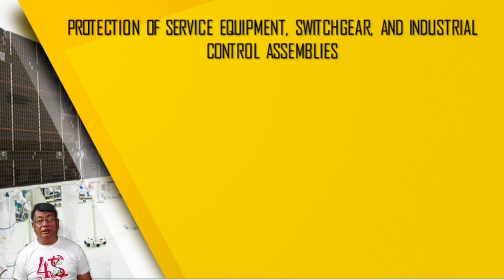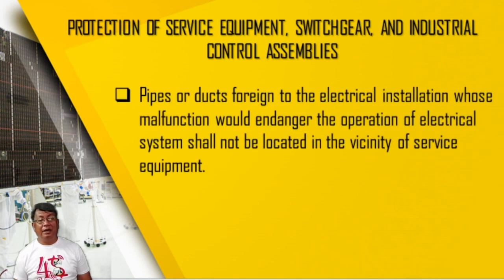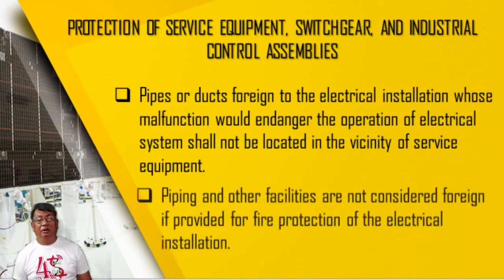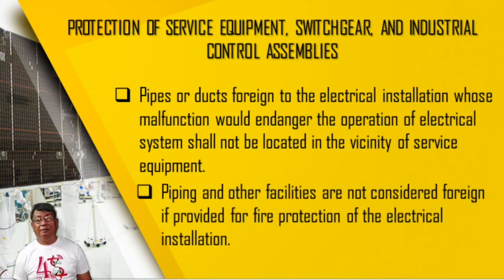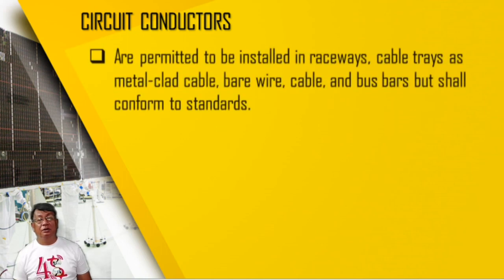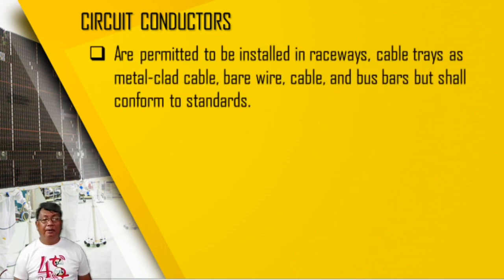Protection of service equipment, switchgears, and industrial control assemblies. Pipes or ducts foreign to the electrical installation whose malfunction would endanger the operation of the electrical system shall not be located in the vicinity of the equipment. Piping and other facilities are not considered foreign if provided for fire protection of the electrical installations. These circuit conductors are permitted to be installed in raceways, cable trays, as metal clad cable, metal cladding, bare wire, cable, and bus bars, but shall conform to standards.